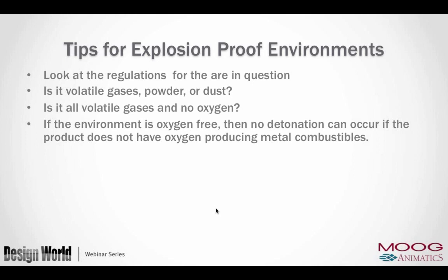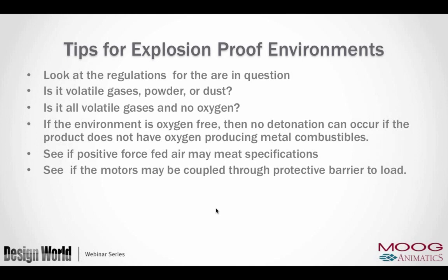Okay, so in other words, you can actually run a non-explosion proof product within a pipeline. See if positive force fed air may meet specifications as well. Okay, in this case, you may just have to feed positive air into the product so it cannot absorb that. See if the motors may be coupled through a protective barrier to the load.